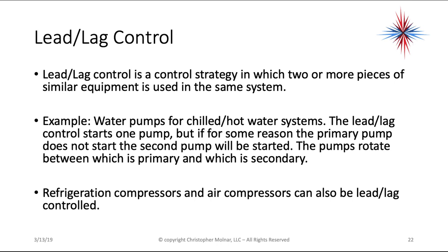Lead lag control is a control strategy in which two or more pieces of similar equipment are used in the same system. A great example is water pumps for a chilled or hot water system: lead lag control starts one pump, but if the primary pump does not start, the secondary pump is started. The pumps rotate between which is primary and which is secondary. Refrigeration compressors and air compressors can also be lead lag controlled.